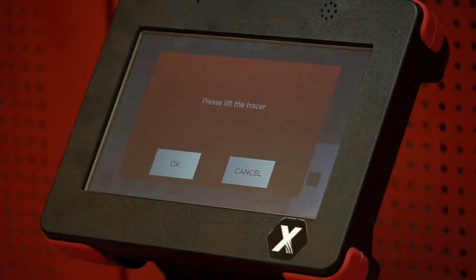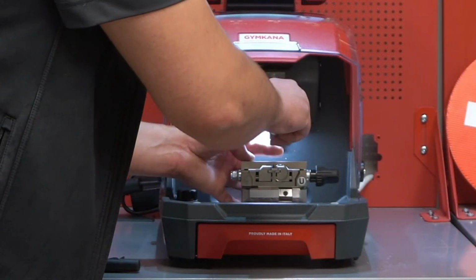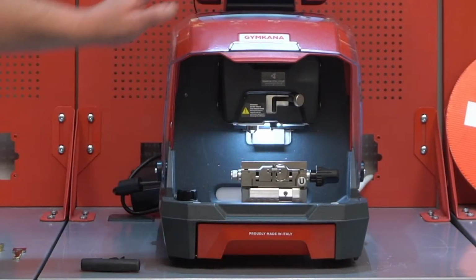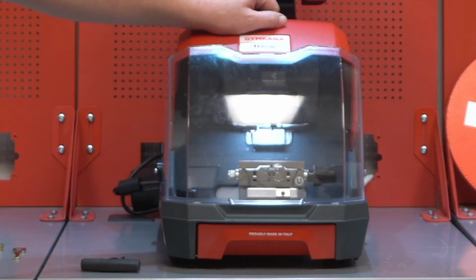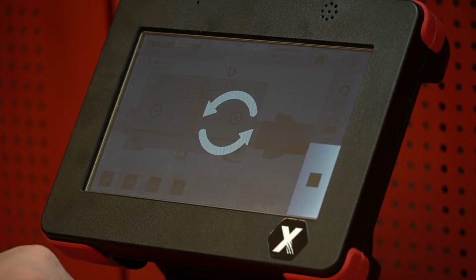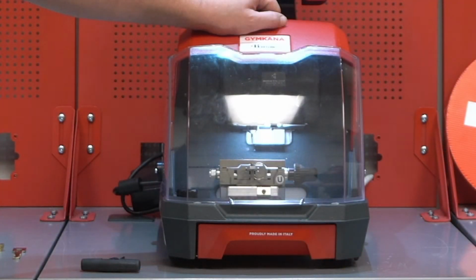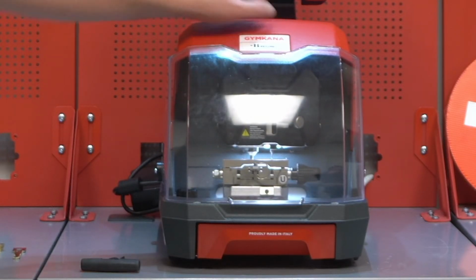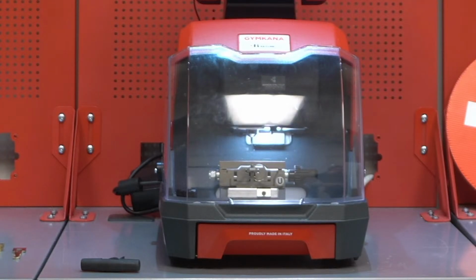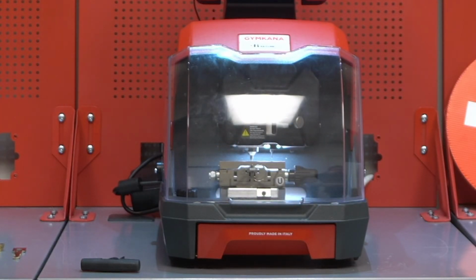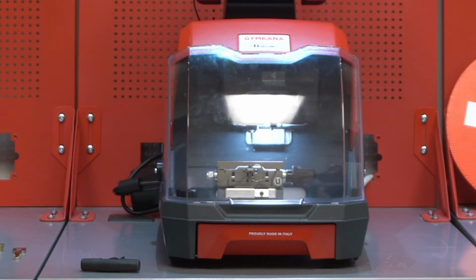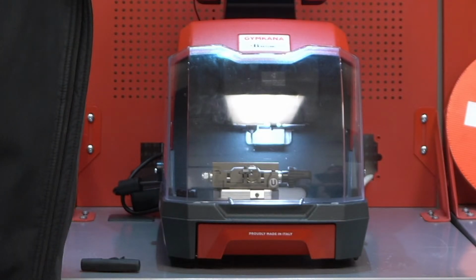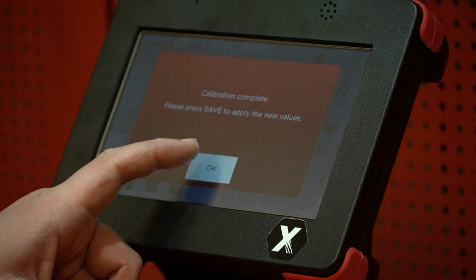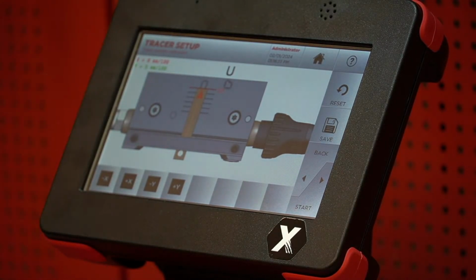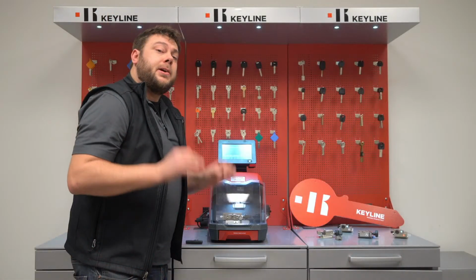Please lift the tracer. So what you do is you open the shield, loosen the tracer knob, lift it up and put it to the right so it's out of the way, and then you close the shield and press OK. And once it's done, calibration complete, please press save to apply the new values. You hit OK, and then your values will always change because it's calibrated to 1/100ths of a millimeter. I have seen it where it doesn't change before, but usually it will change.